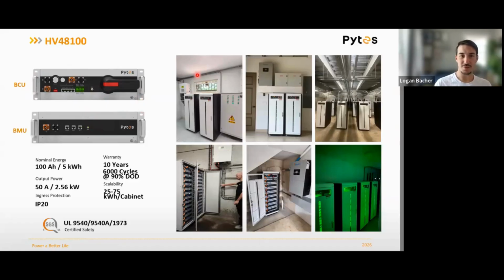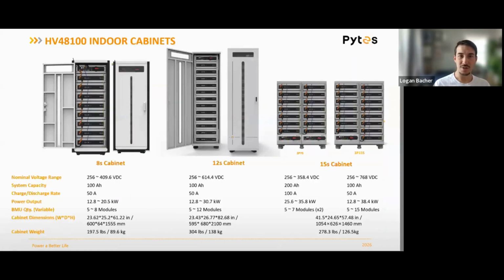This first solution is indoor rated. All these cabinets are indoor only. The batteries themselves have a half C rating, so right out of the 100 amp hour capacity, we can charge and discharge continuously at about 50 amps, or about 2.5 kilowatts, backed by a 10-year warranty, 6,000 cycles at 90% depth of discharge. And then depending on the cabinet model, you've got different energy capacities available.